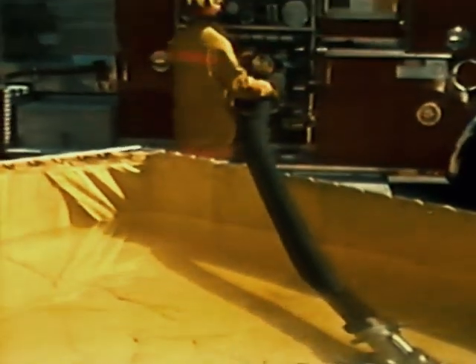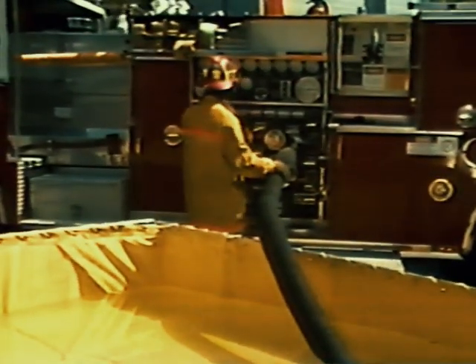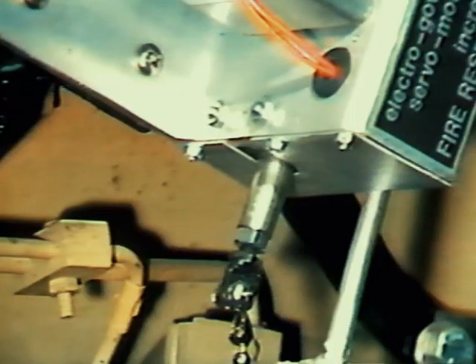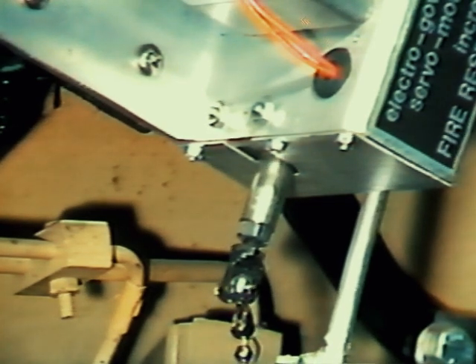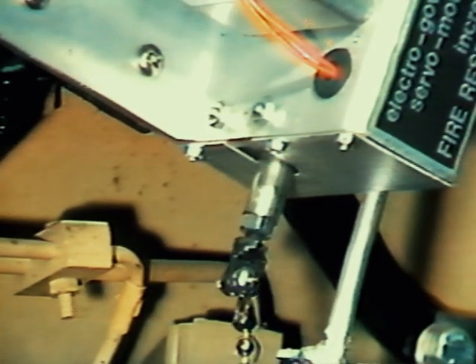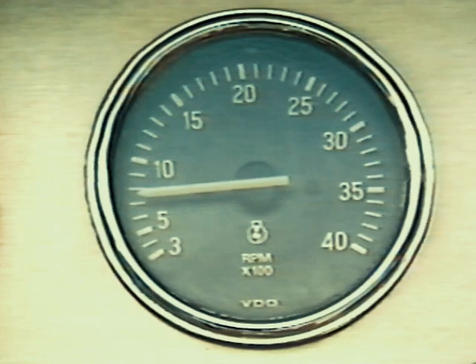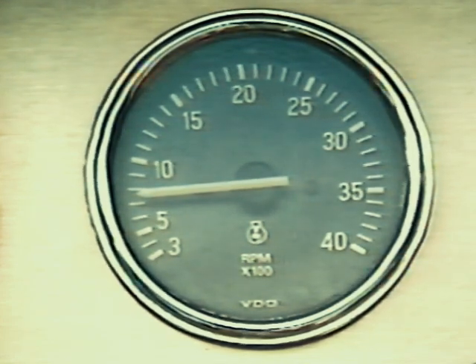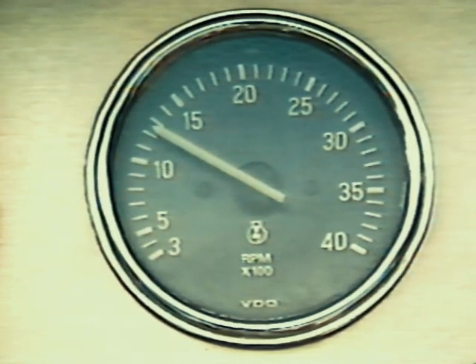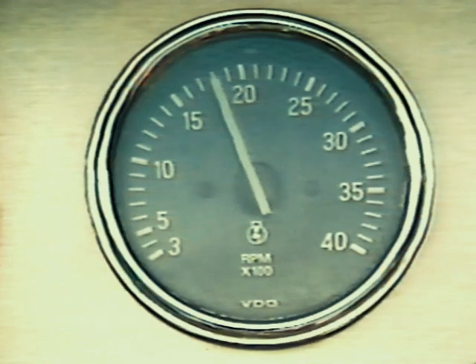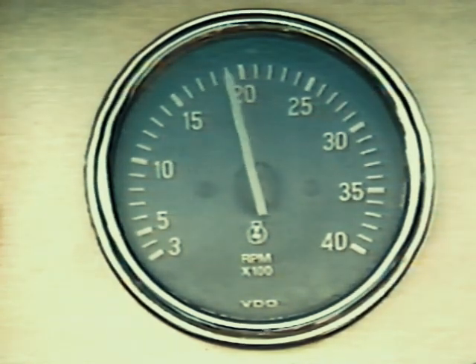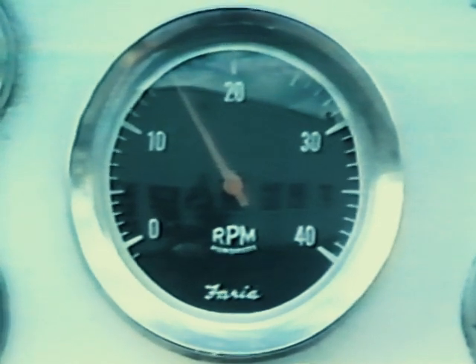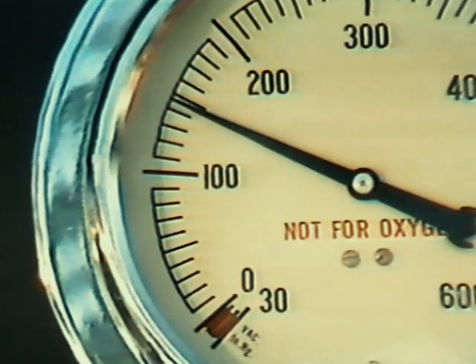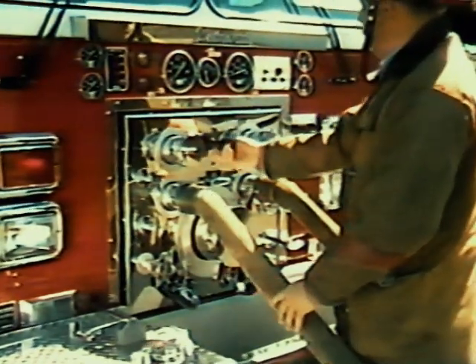On some apparatus, you must be careful. A loss of water at the water source will cause the pressure control governor to increase the speed of the engine to maintain the set pressure. Without an intake source of water, the action of the governor may cause the engine to overspeed, which could damage the engine or pump. Monitor the system closely. If the engine increases speed without an increase in pressure, manually slow the engine with the throttle control.